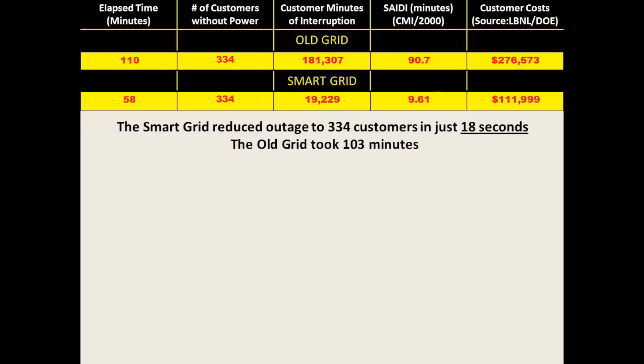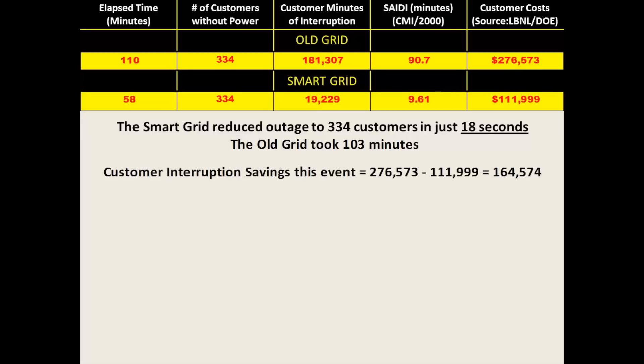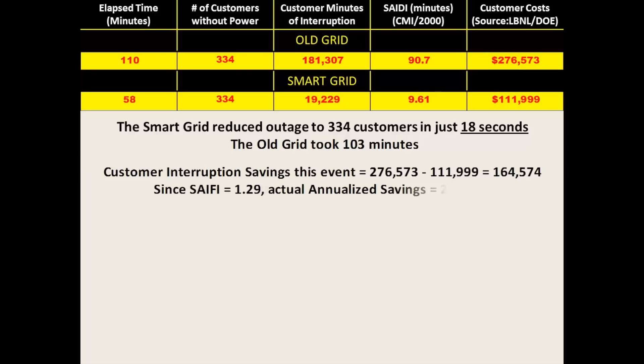By doing so, the smart grid cuts electricity customer costs by almost $165,000 for this incident alone. Recall that the interruption frequency index SAIFI was 1.29, meaning the average customer sees 1.29 outages per year — so the actual annualized savings are even bigger: over $210,000.